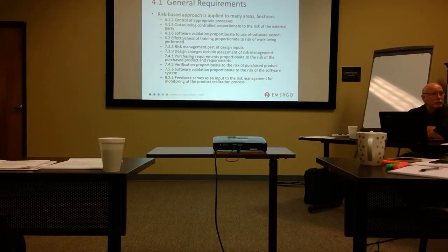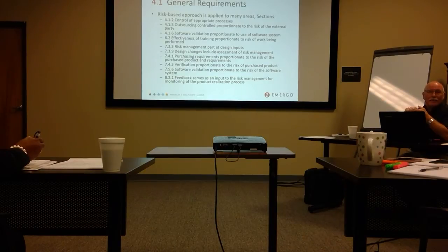Purchasing. What level of control do I need? Now, purchasing is considered separately from vendor qualification and monitoring. Purchasing has fairly simple requirements. One, and this is obvious, document what you are intending to buy, because obviously if you don't, you're not going to get what you need, including anything in specifications, grades, so forth and so on. The other requirement is that in your purchasing documentation, however you elect to do it, you need a statement in there that says you, the supplier, may not change anything without my prior approval.